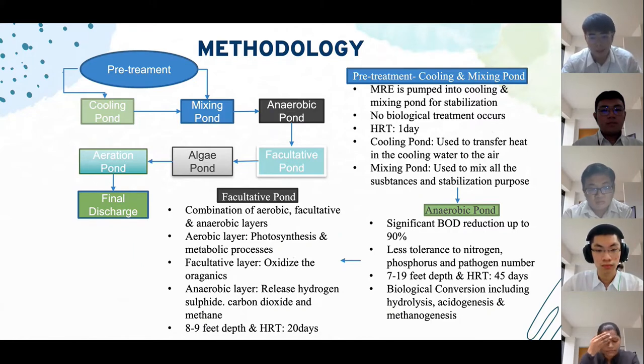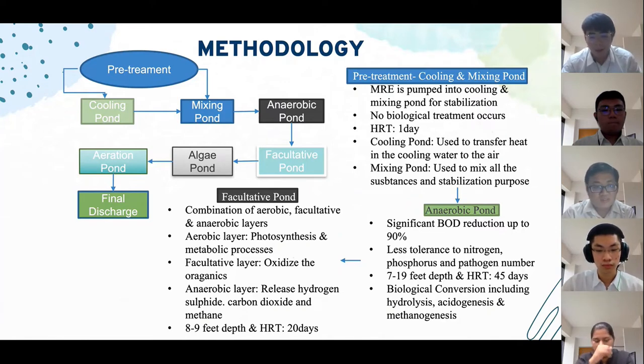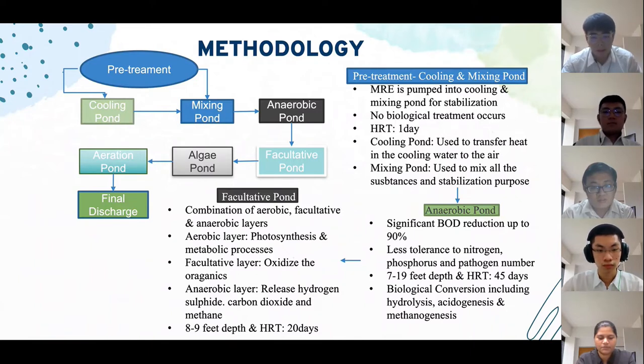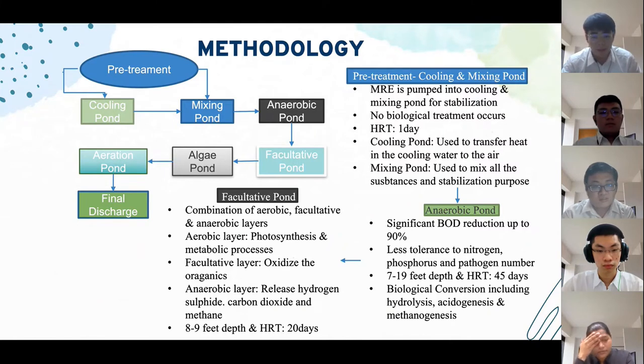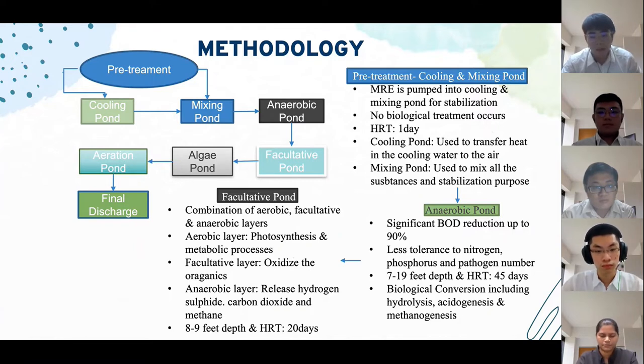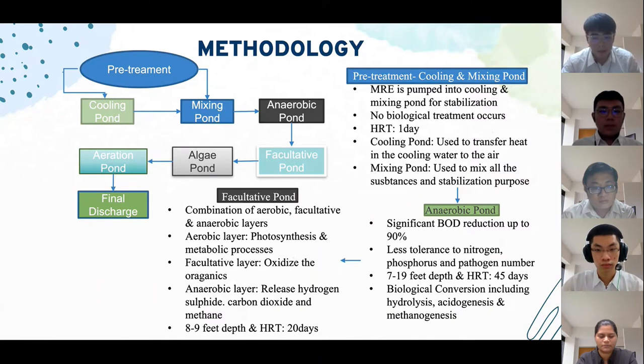The second pond is the facultative pond. In the facultative ponding system, there are three distinct layers: aerobic, facultative, and anaerobic. At the first layer, algae use carbon dioxide, ammonia, phosphates, and sunlight to encourage photosynthesis and metabolic processes, releasing oxygen. At the second layer, facultative bacteria grow rapidly and oxidise organic matter in the middle zone. At the third layer, with total absence of oxygen, anaerobic bacteria consume settled solids and organic matter, releasing hydrogen sulphide, carbon dioxide, and methane. Facultative ponds are usually 9 feet deep with an HRT of 20 days.